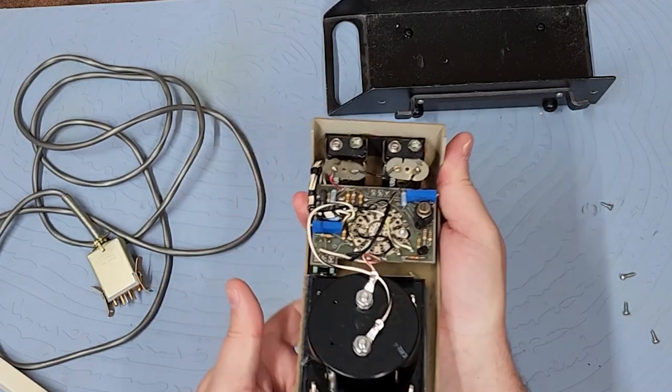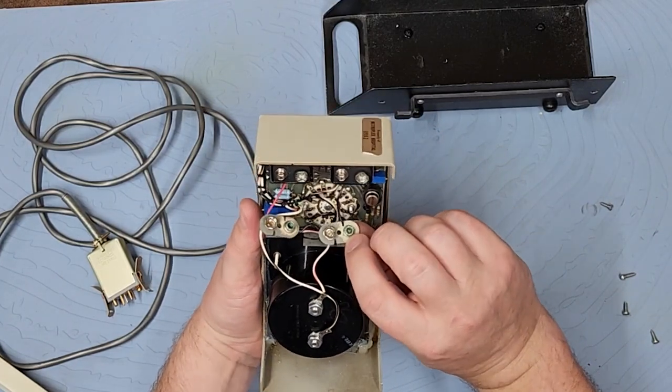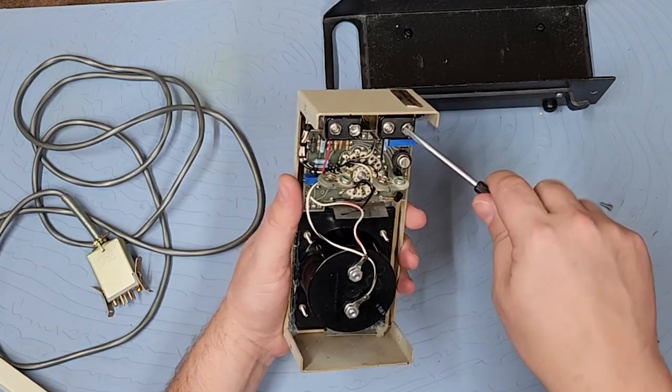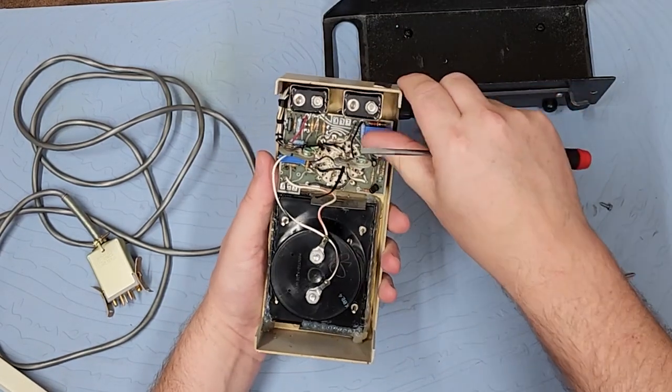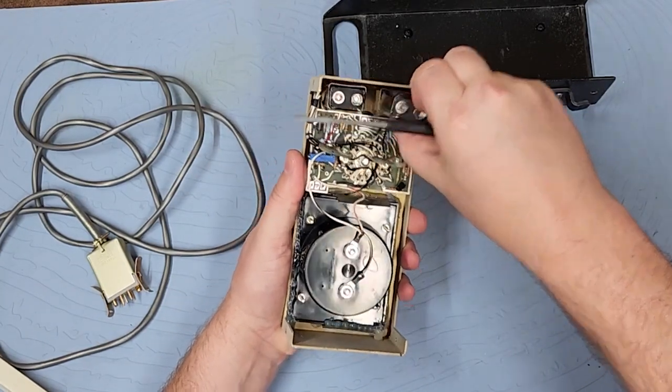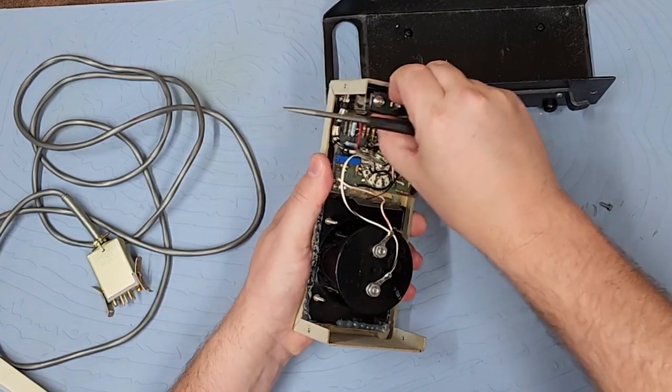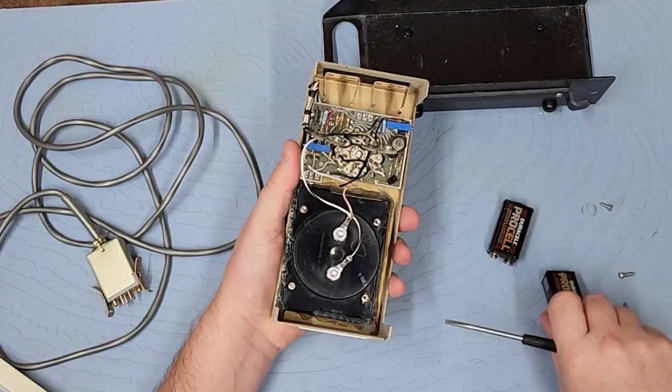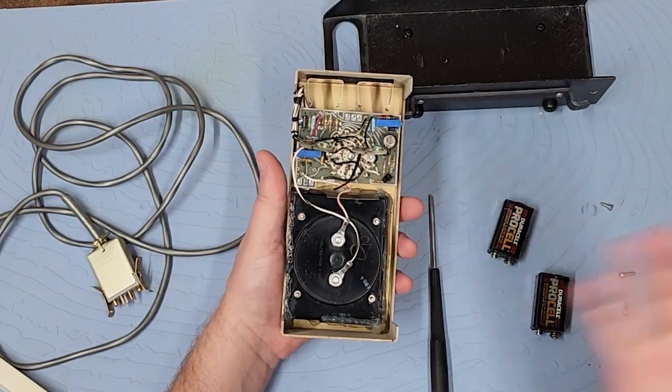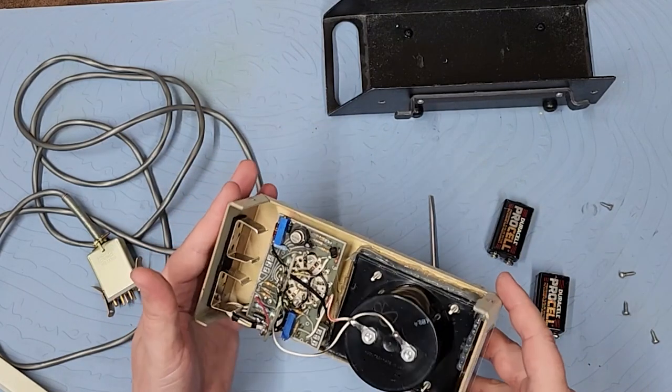I'm trying to be careful and it's still really difficult. So look at that, have you ever seen a piece of test equipment like that? We do have some corrosion, so I'll clean both of those up. If you're ever storing your medical test equipment, take the batteries out if you are not going to use it for another PM year. I've got all my test equipment with the batteries out sitting in the case.